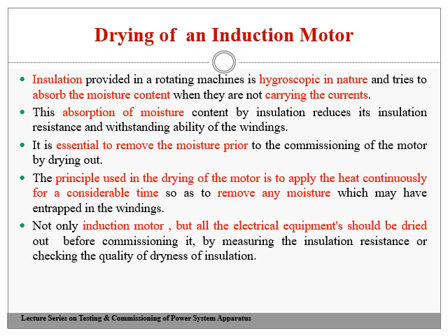Not only the induction motor, but all electrical equipment, all electrical rotating machines and static machines, are to be dried out when the insulation resistance becomes less than the permissible limit specified by the Indian standards. Once the insulation resistance is measured, if it is according to the Indian standards for a particular capacity of induction motor or electrical equipment, we do not require any drying process.